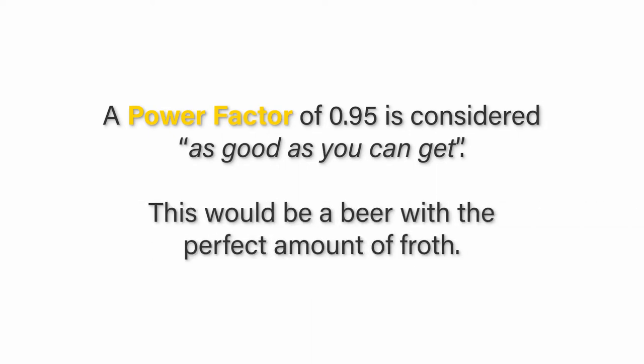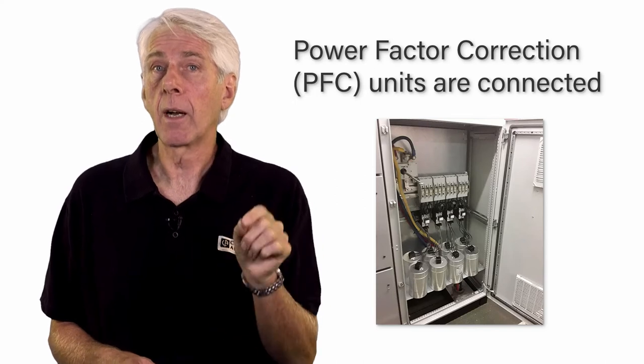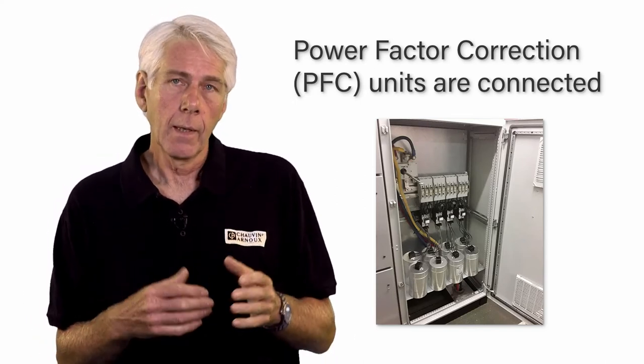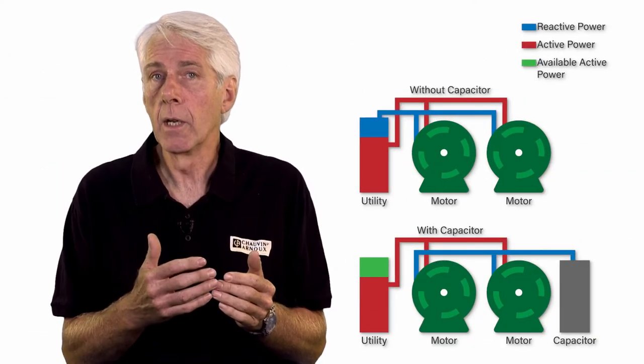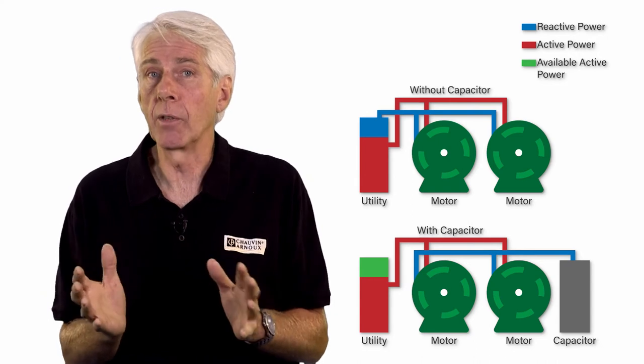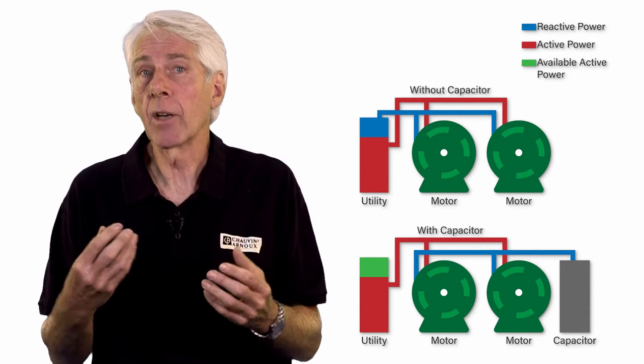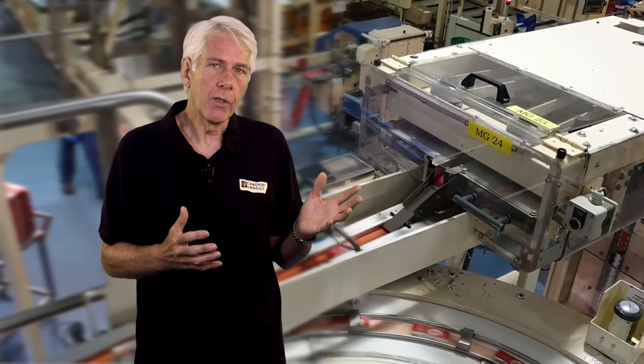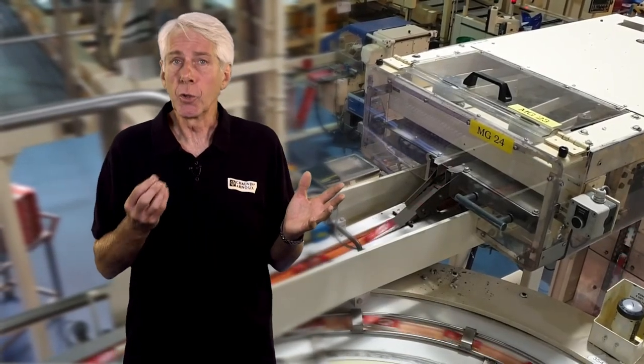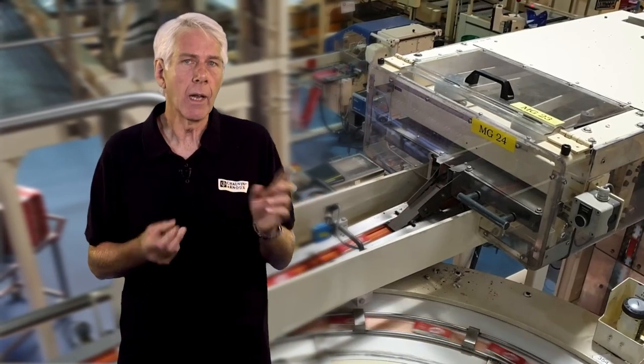To achieve a power factor of 0.95, power factor correction or PFC units are connected to the installation. In its simplest form, this consists of a selection of capacitors of calculated values that automatically switch in and out as changes in the operating load require. The capacitance basically counteracts the effects of the inductance in the load. With modern equipment it's not quite as simple, due to the need to consider harmonics and other power quality issues caused by non-linear loads.